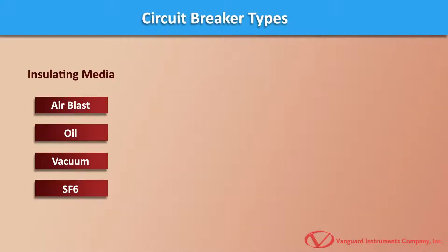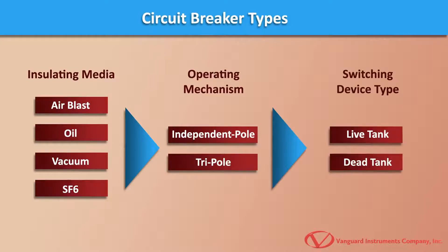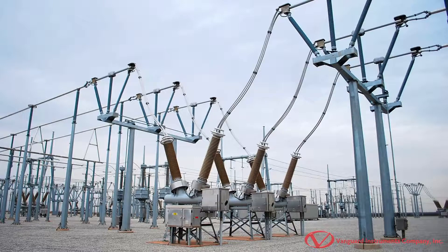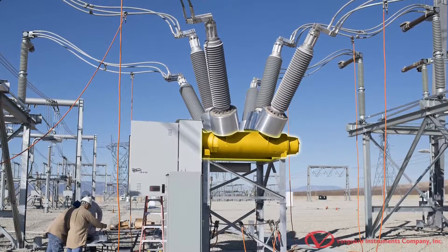Substation breakers are classified as either independent pole or tripole. They are further classified as live tank or dead tank breakers. Independent pole breakers feature a separate operating mechanism for each phase, while tripole breakers use a common operating mechanism for all three phases.